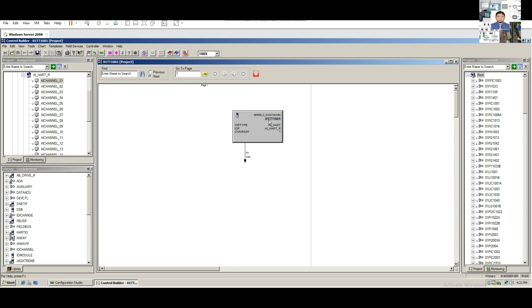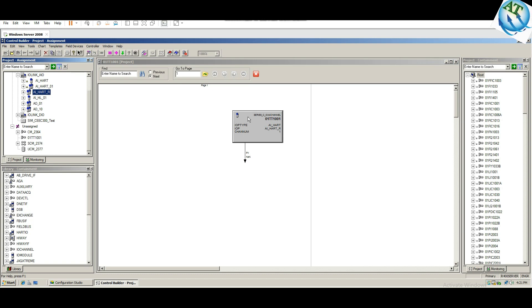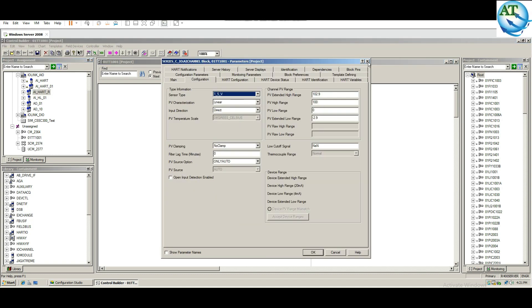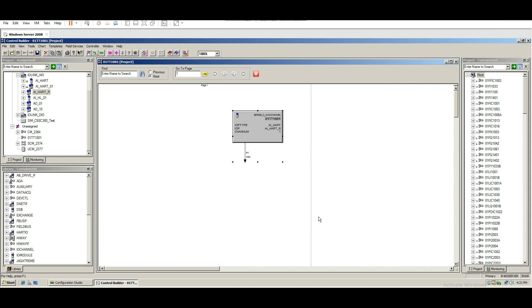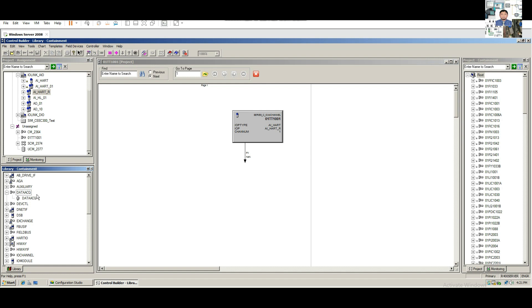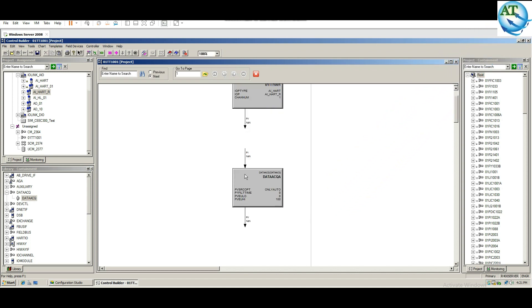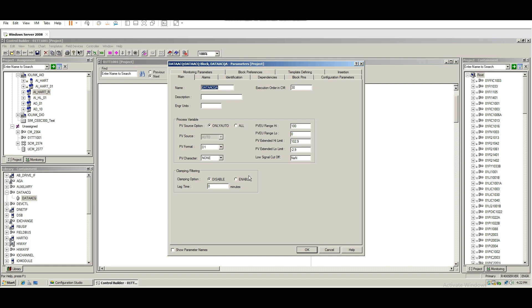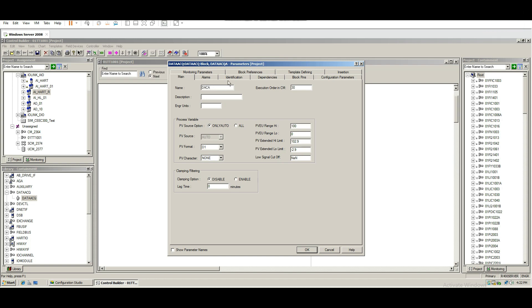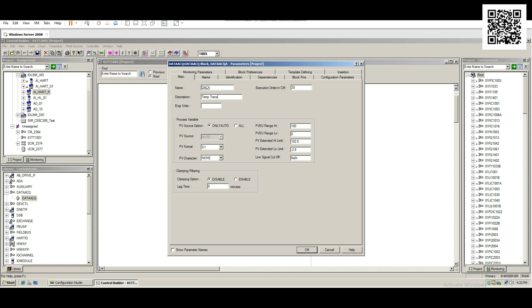Our block is now renamed — it is 01 TT1001, rename is completed. Now we need to make the scaling factor for display. The block range is 0 to 100, but our transmitter that we want to display in the DCS system has a range of 0 to 500. So we have to select another block — the Data Acquisition (DA) scaling block. Press and release to insert it. Now double-click on this transmitter block. Here you can put the same name, 01, and it is the DA data block system.